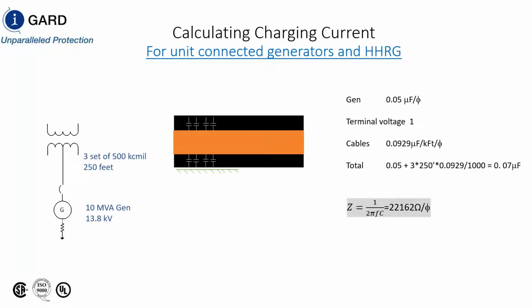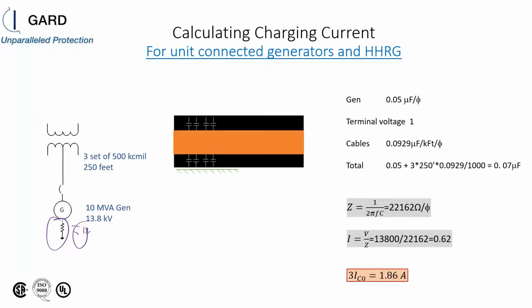Going through the formulation, we have 22,000 ohms per phase. Your current is 0.62 amps. 3 times that is 1.86. So realistically, if you had a unit connected generator, you could put a 5 amp resistor in here, limit the fault current to 5 amps, and not worry about a hybrid high resistance grounded system. But if you have a medium voltage bus connected system, then you have to put in additional current, because once that breaker is closed, you're picking up the charging current of the rest of the system.